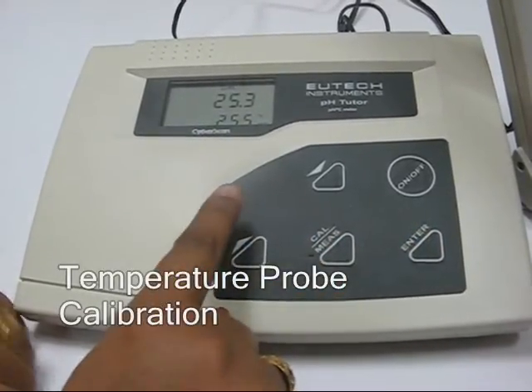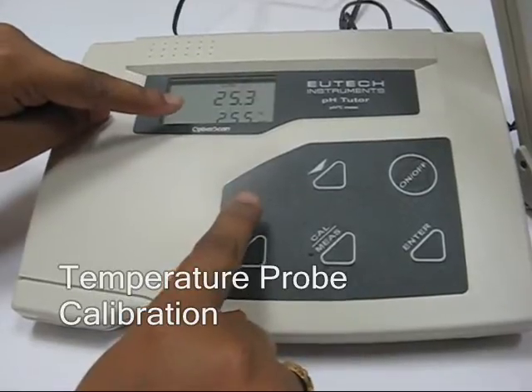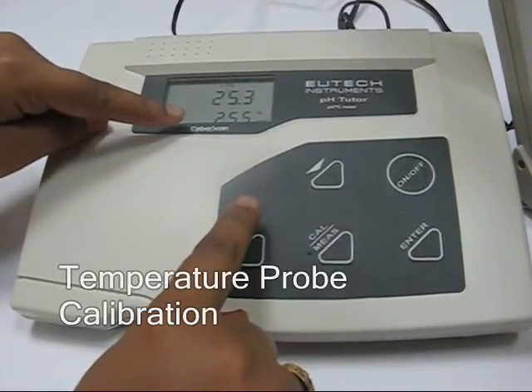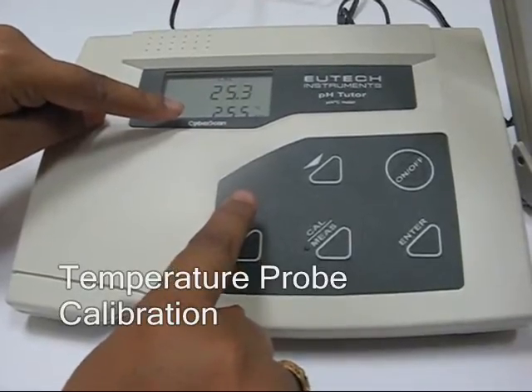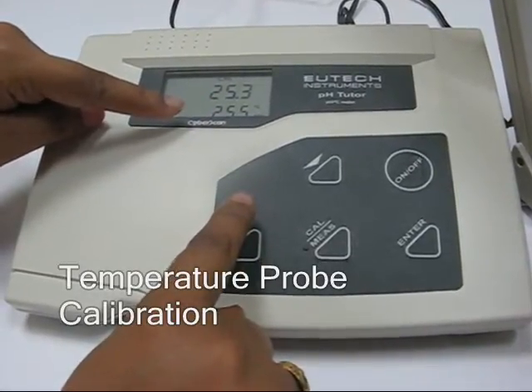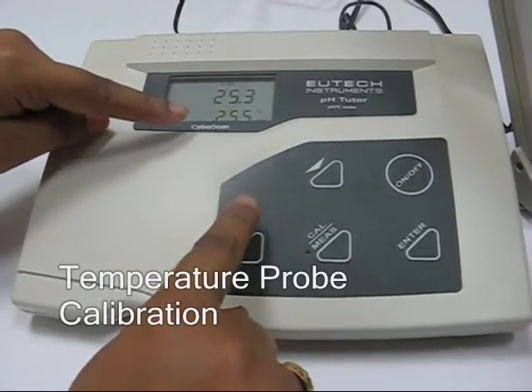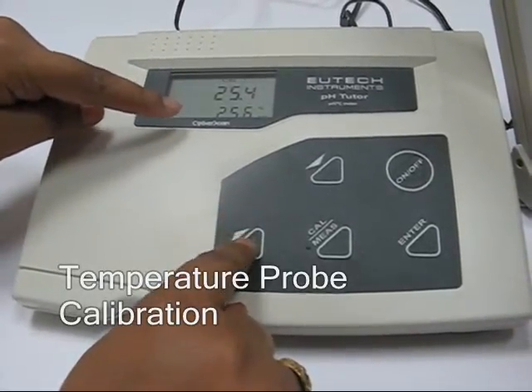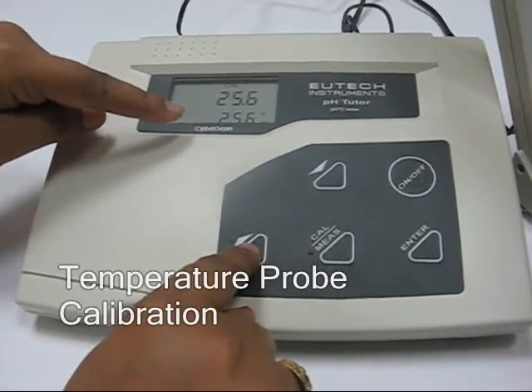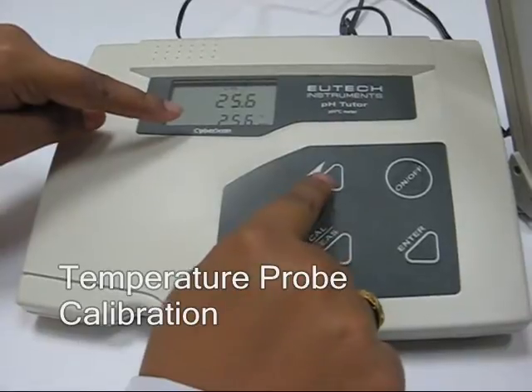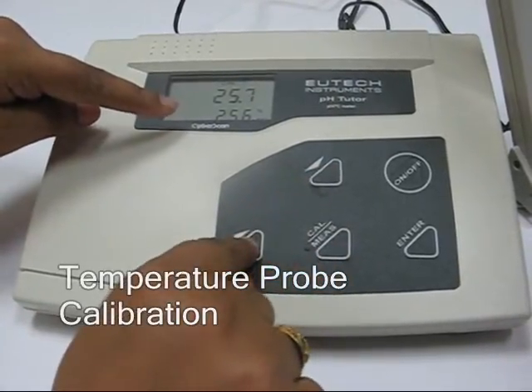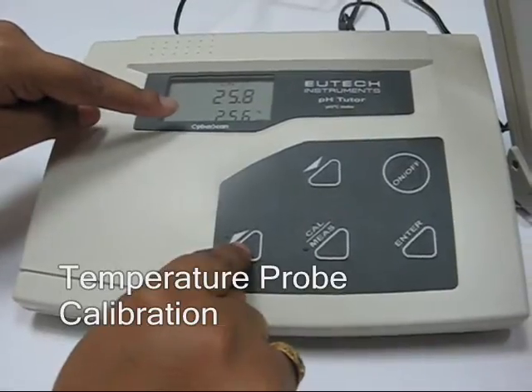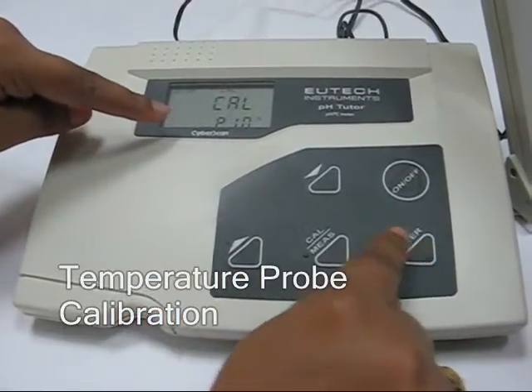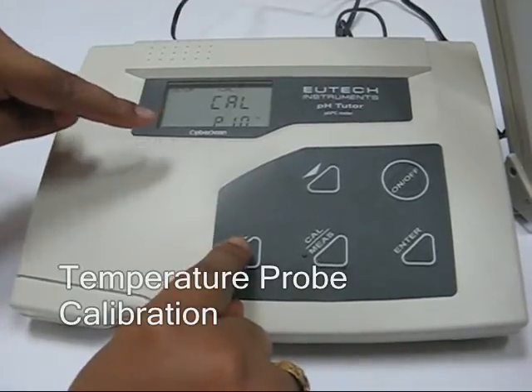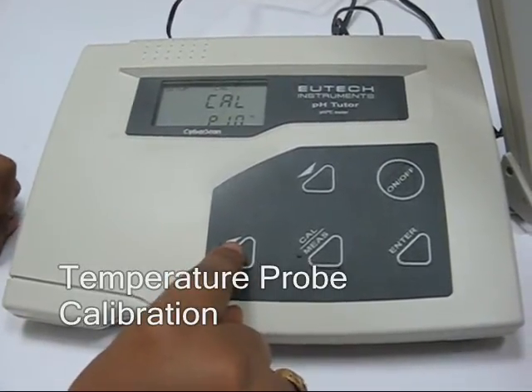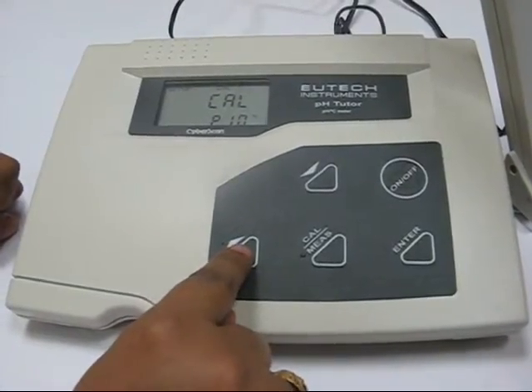You now see two displays. One is the default value, and the other one is the value from the last calibration. You now have to adjust the temperature reading to the actual value which you can get from a reference thermometer by pressing the up or down key to match with your reference temperature. Let's assume for a minute that the actual temperature is 25.8 degrees. So you keep pressing until you come to 25.8, and then you press the enter key. This confirms the calibration. So now you have calibrated the temperature probe to the correct temperature, which in this case was 25.8. That's what program 1.0 is all about.